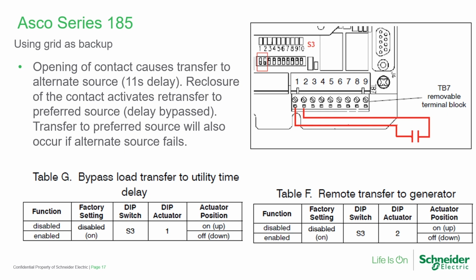Once connection to the grid is made, the loads will be supported by the grid until the batteries are charged to whatever battery condition the programmer deems appropriate, either voltage or state of charge. If you're using our battery monitor, you can partially charge the battery to give the solar chance to pick up, so you don't need to leave it connected until the batteries are fully charged. The aux port is completely programmable. Once the desired battery level is reached, the aux port will de-energize, allowing the relay contact to open, and connection is made to the alternate source, which is the XW Pro system. Keep in mind this only works with DC coupled systems.